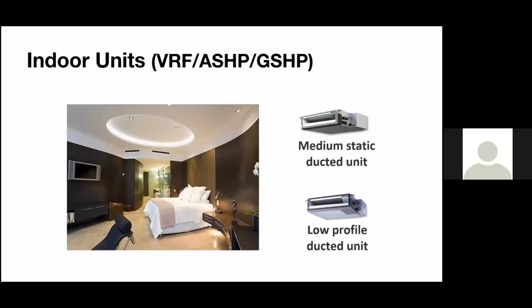And then you look at your low profile ducted unit. This is probably like 7 to 9 inches tall. What's great about this, as the picture shows, is that you have a soffit. Basically the ceilings drop down low, and one of those low profile ducted units is sitting in this hotel room. You see that all the time, and barely any ductwork, but it fits there perfectly and does provide heating and cooling to this hotel. Something like a medium static would probably be a little too tall, but low profile has the perfect fit. And that static pressure is only about 0.3 inches there.